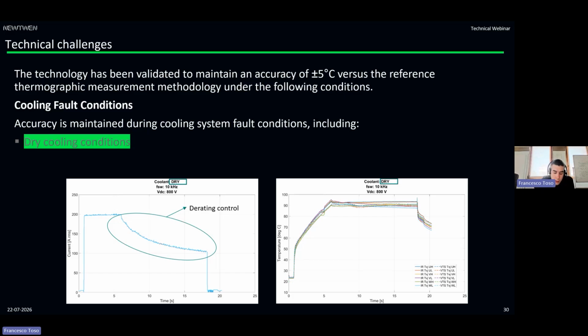So in this case, you can see the control architecture in place using a closed loop with the junction temperature, which is derating the current to a dynamic limit such that the junction temperature is safety driven, within in this case 90 Celsius degrees. So how does the controller behave? The controller in the first seconds understands that the dynamic is quite different from the normal operating cooling condition. So the controller sets a new temperature limit, from 175 that was before, to 90 Celsius degrees. So there is a new temperature safety limit set. And then once the junction temperature reaches that limit, there is the derating current condition that you can see on the left, lowering the current such that you keep the maximum junction temperature in the system constant. This has two main advantages.